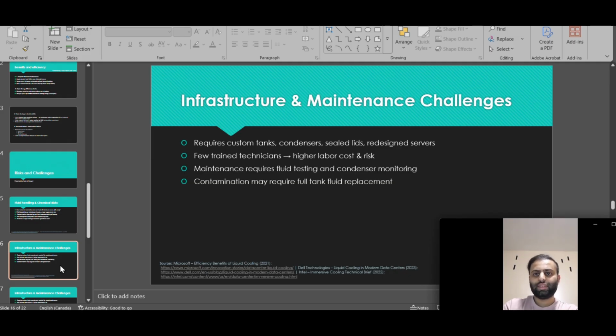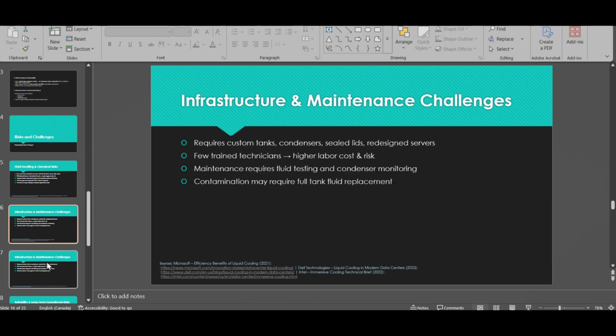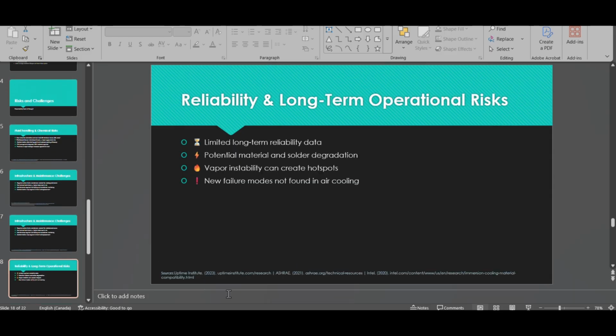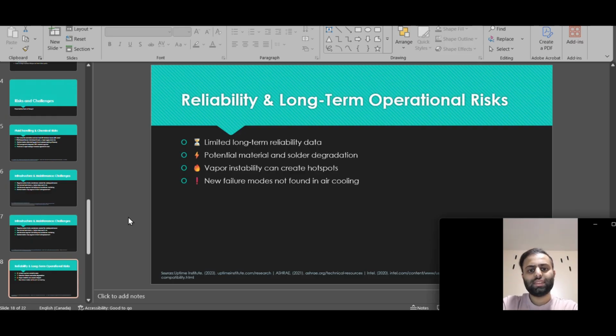One more challenge they face is reliability and long-term operational risk. Two-phase immersion is still relatively new, and there isn't enough multi-year data on how components behave after years of exposure to boiling fluid. There are also performance risks such as vapor bubble formation or film boiling, which can create hotspots and reduce cooling efficiency. In addition, immersion introduces new failure modes like vapor lock, seal failures, and unstable boiling under heavy workload.